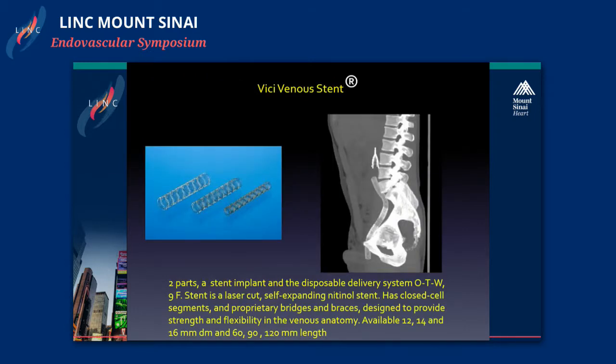The Veniti VICI Venous stent is a two-part stent with an implant and a disposable delivery system over the wire, 9 French. It's a laser-cut, self-expanding nitinol stent, provided with a closed cell design, and has proprietary bridges and braces designed to provide strength and flexibility in the venous anatomy. In the venous anatomy, you need a lot of flexibility to prevent crushing and deformation of the stents. It's available in 12, 14, and 16 millimeters, and in 60, 90, and 120 millimeter lengths.